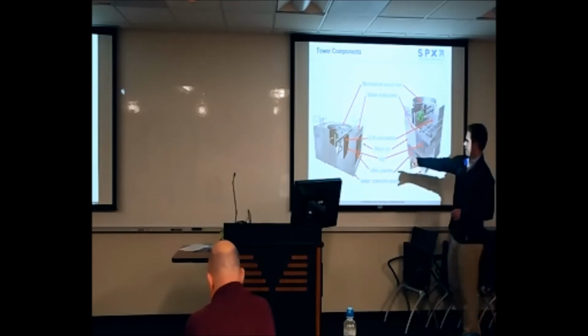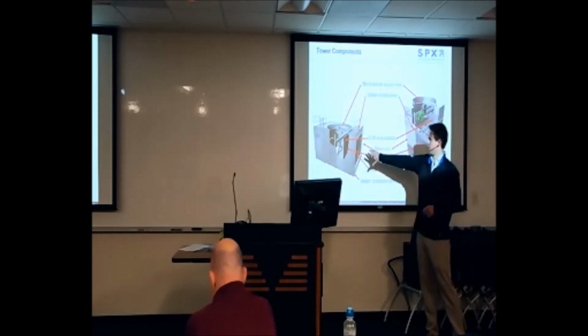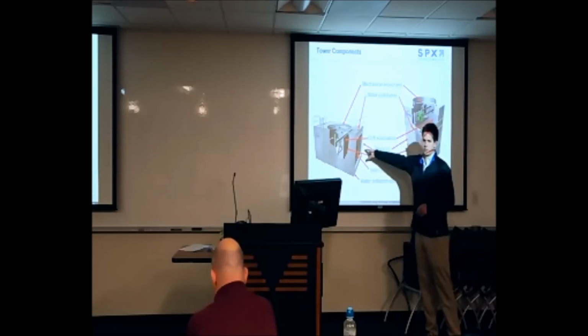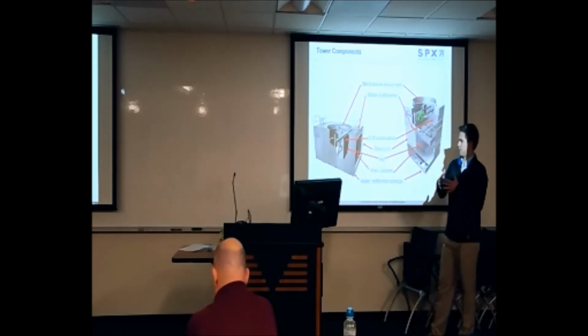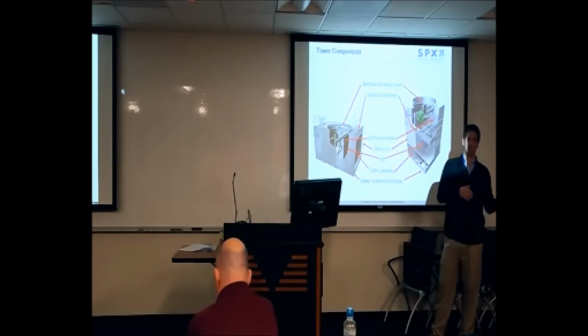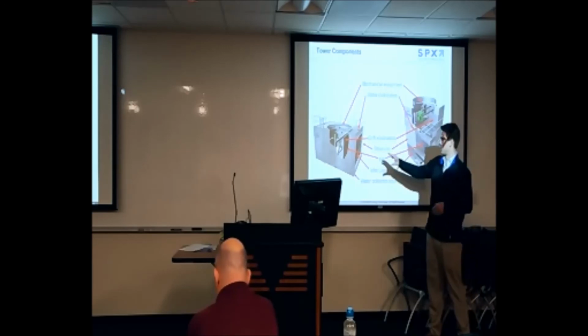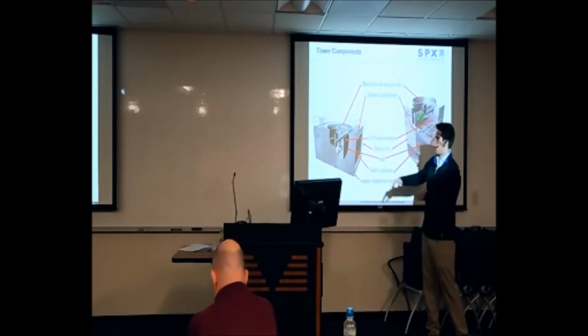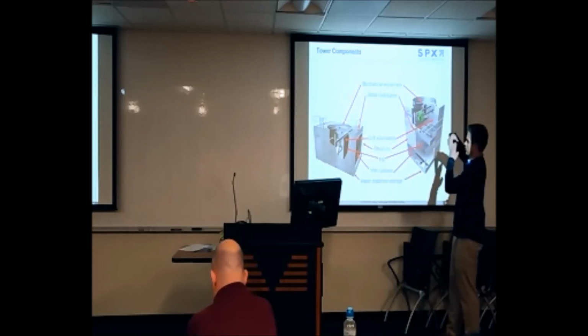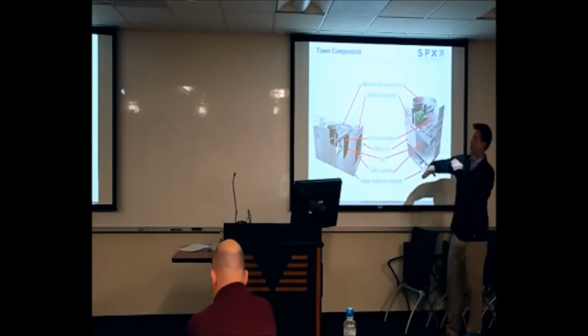We also have, integral to the fill, louvers, which are the first point of contact for the air. The purpose of the louvers is to keep the water inside the tower. Without louvers, the water would just fall out of the fill. It may fall in the basin. It may fall out of the tower completely. So the louvers, which are connected to the fill, are angled such that water that falls on the louvers will be directed back inside the tower.